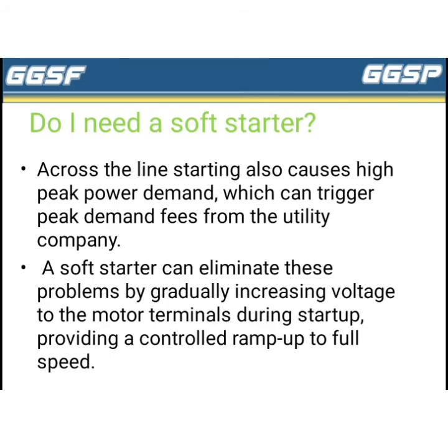Do I need a soft starter? Across the line starting also causes high peak power demand, which can trigger peak demand fees from the utility company. A soft starter can eliminate these problems by gradually increasing voltage to the motor terminals during startup, providing a controlled ramp up to full speed.